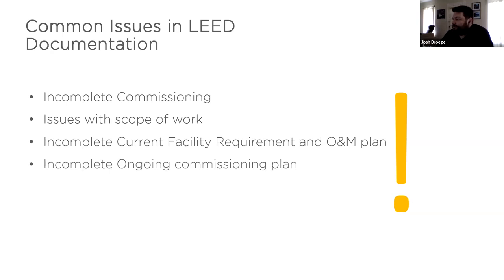Similarly, we see issues with incomplete ongoing commissioning plans and incomplete functional performance tests. For example, did the functional performance test of an air-cooled chiller or air handling unit step through all the steps in the sequence of operations? We look into those details to make sure the tests were done correctly.